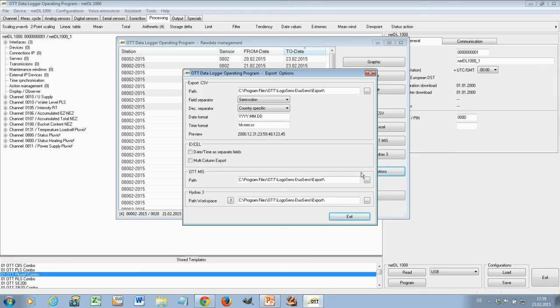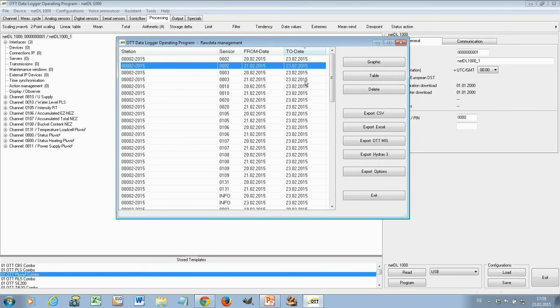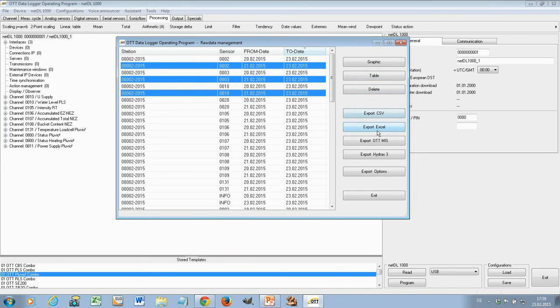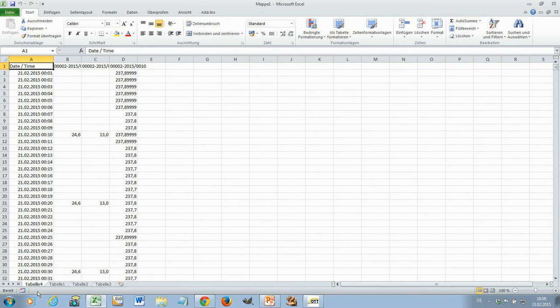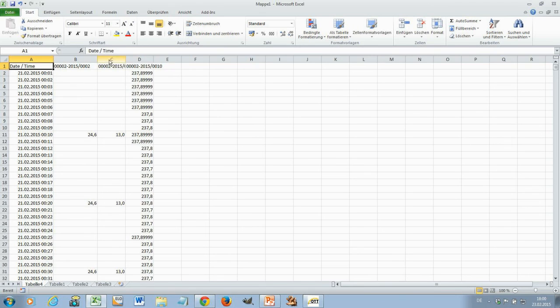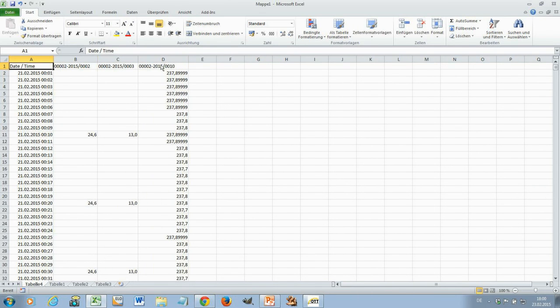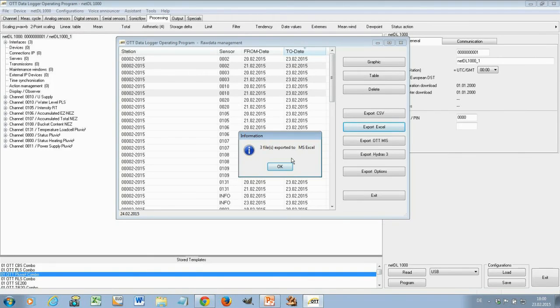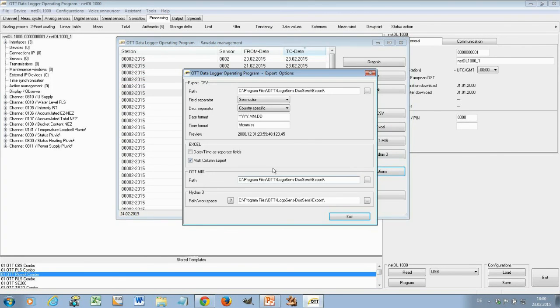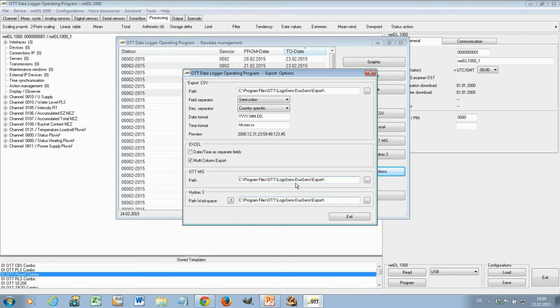Let's close that again. In export options you can also say multi-column export. You check this box and we do the same thing again. Let's take only three sensors, export to Excel. Now the difference is we have the three values not in three different tabs but all in one Excel sheet. So those are the three sensors or channels I've selected. So this is chosen here by multi-column export or not. What you also can do if you do CSV export, you can choose here the field separator, the decimal separator, the date format, time format and so on. You can define the path where the data is exported to. The same here if you do a MIS file or a Hydras 3, you can choose here the path where the data is exported to.